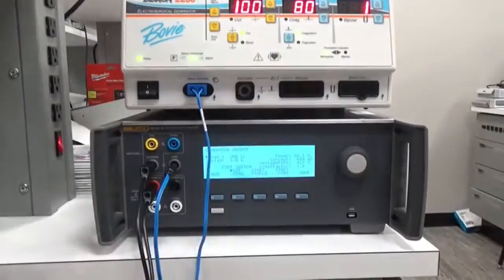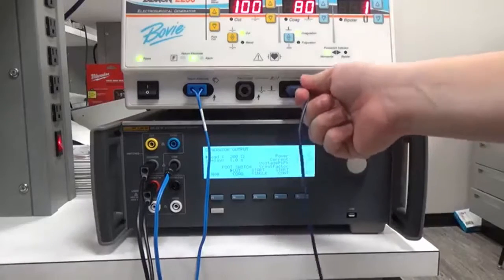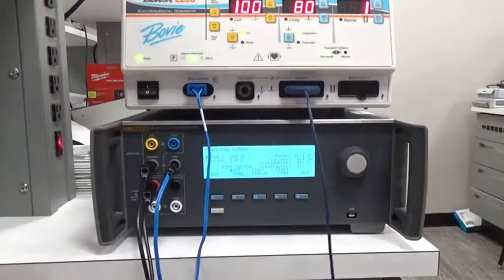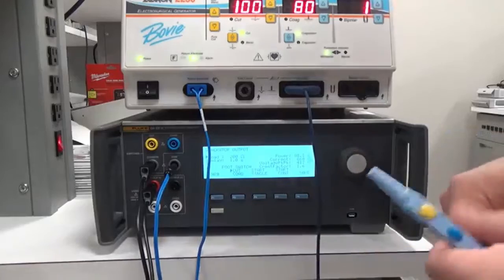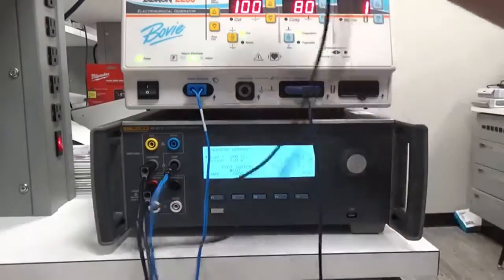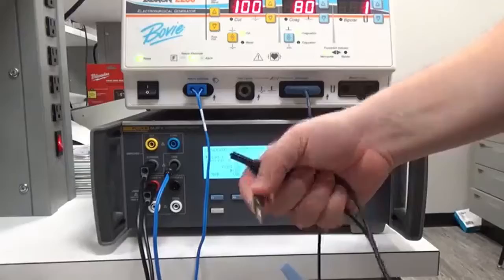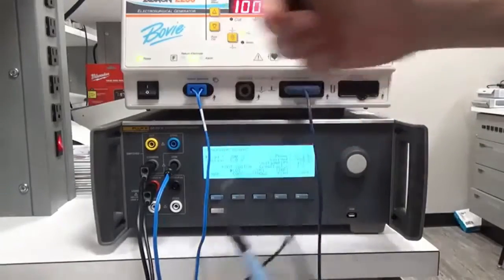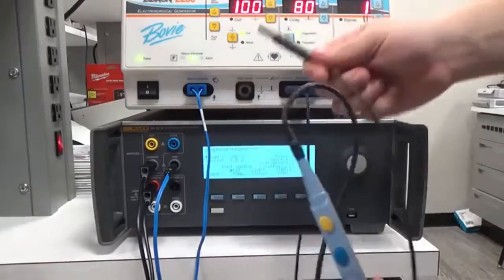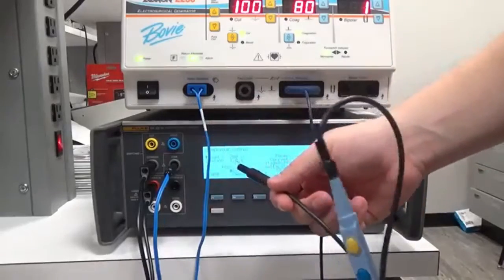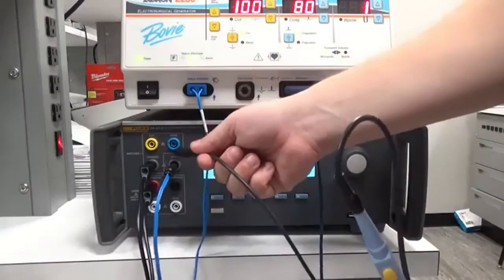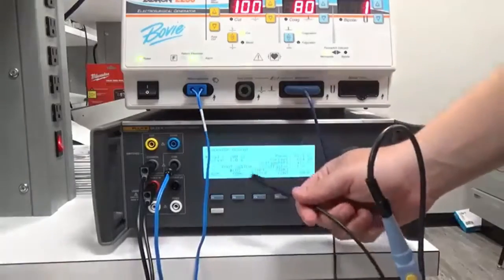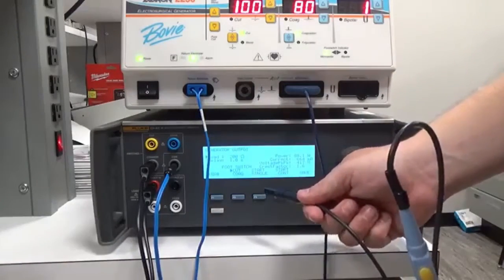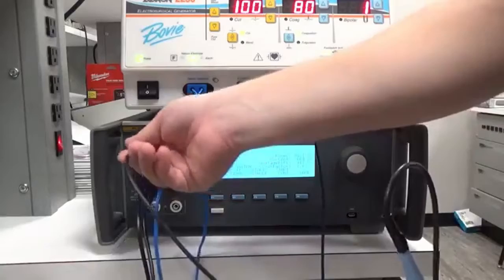So what I'm doing now is I'm grabbing a monopolar pen. I'm going to connect that pen, as we normally would, into the monopolar port. But instead of having a blade at the end, like I was actually going to be using the electrosurgical pen here, I'm actually going to be taking a cord that has a pin on the end. I'm going to be sticking that into the ESU pen. I'm going to take the other end and I'm going to connect it to any port, cut or coag, depending on what test we're doing. I have cut selected on the analyzer, so I'm just going to go ahead and connect that to the cut jack there.